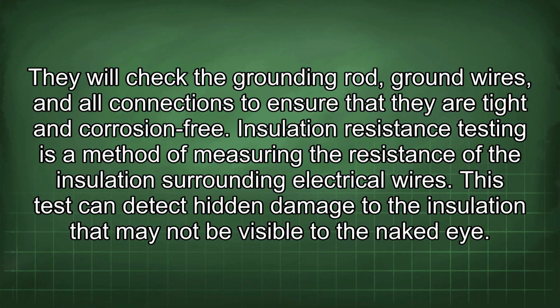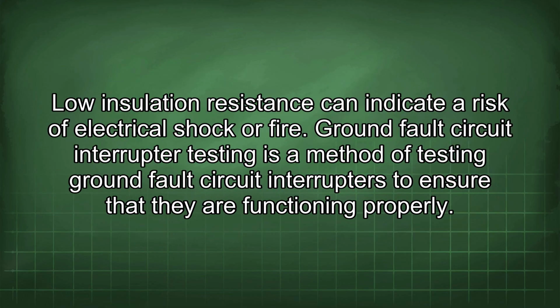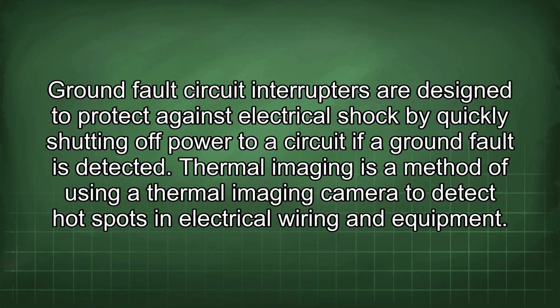Insulation resistance testing is a method of measuring the resistance of the insulation surrounding electrical wires. This test can detect hidden damage to the insulation that may not be visible to the naked eye. Lower insulation resistance can indicate a risk of electrical shock or fire. Ground fault circuit interrupter testing is a method of testing ground fault circuit interrupters to ensure that they are functioning properly. Ground fault circuit interrupters are designed to protect against electrical shock by quickly shutting off power to a circuit if a ground fault is detected.